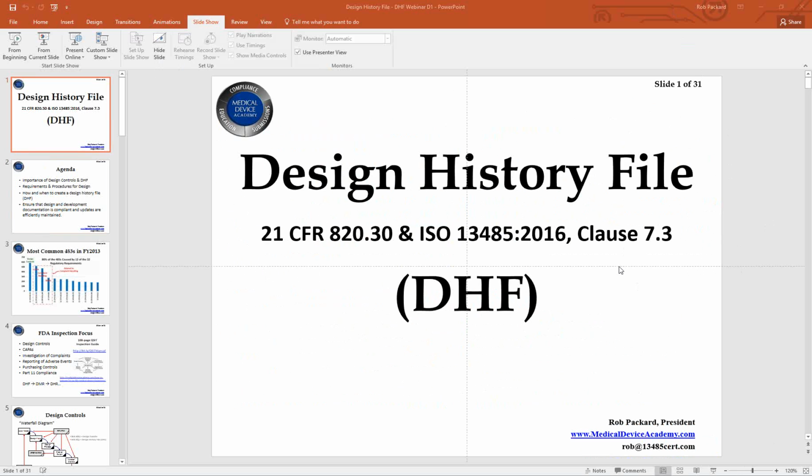So you would probably have DHF responsibility, and you would split the DMR responsibility between your two companies, but you would probably want the authority to review and approve, and the FDA wants any changes that they make you're notified of in writing, and you have a chance to review and approve those and make sure they're validated. So that would be, once again, part of that change control process and part of the new requirement for supplier controls.